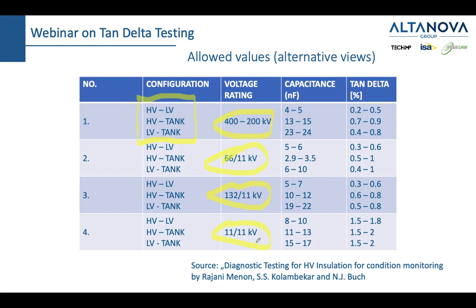In that case, since we don't have very high voltage levels here, the tan delta can also be higher, even up to 2%. But what you need to observe is that high voltage, low voltage is always the one which needs to be the smallest. The tan delta for this insulation needs to be the strongest because this is, let's say, the important one. Now, I hope this part is clear. You are encouraged to ask questions.